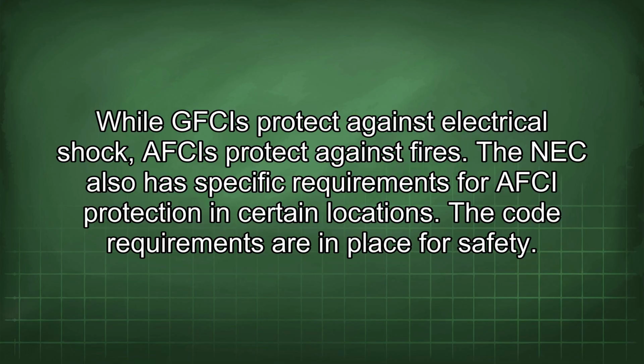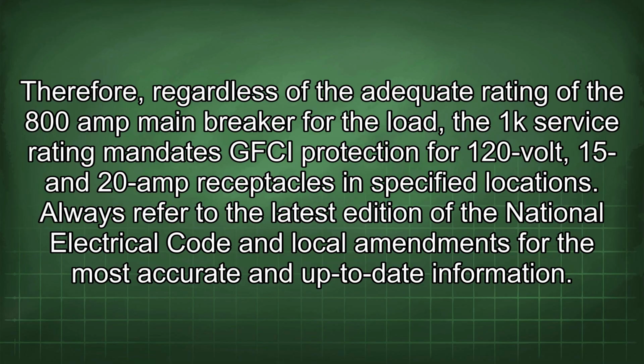The NEC also has specific requirements for GFCI protection in certain locations. The code requirements are in place for safety. Therefore, regardless of the adequate rating of the 800 amp main breaker for the load, the service rating mandates GFCI protection for 120 volt, 15 and 20 amp receptacles in specified locations. Always refer to the latest edition of the National Electrical Code and local amendments for the most accurate and up-to-date information.